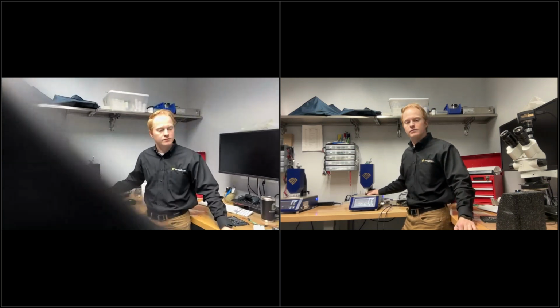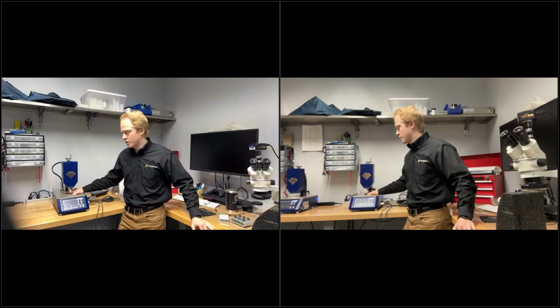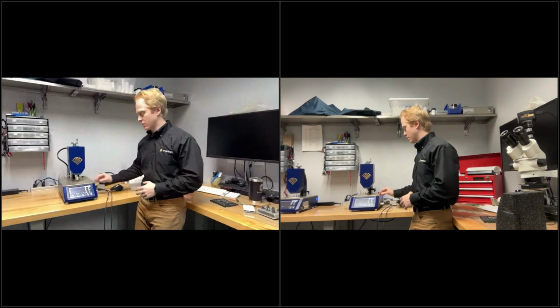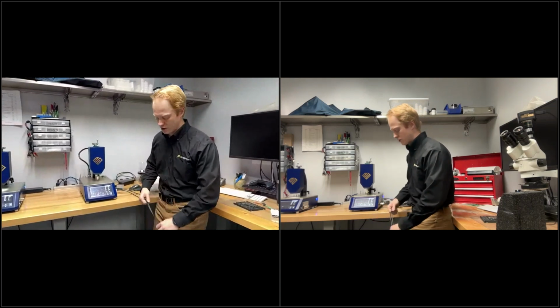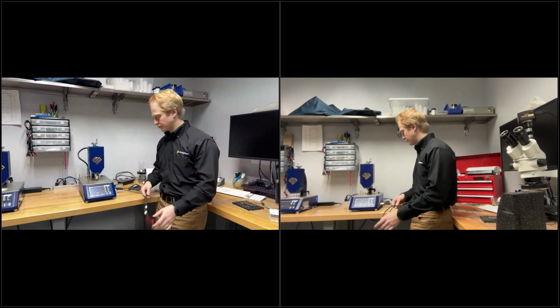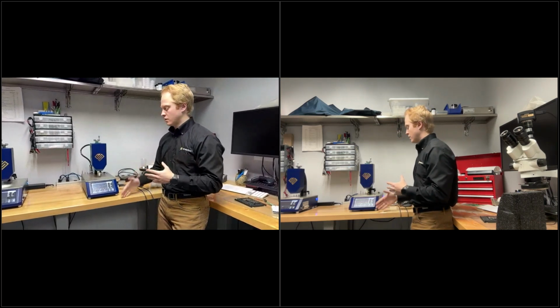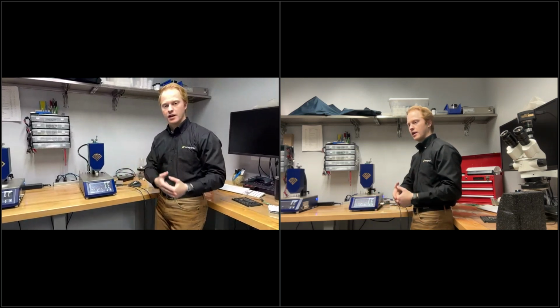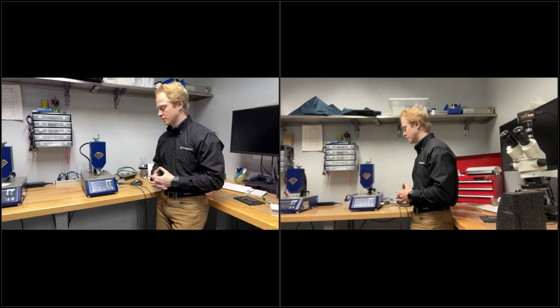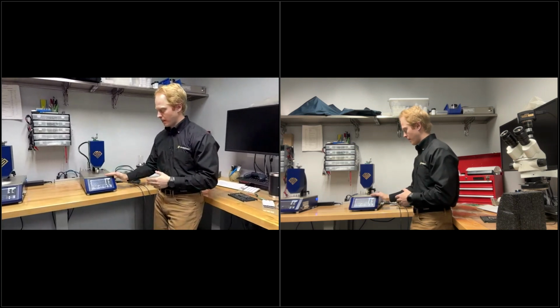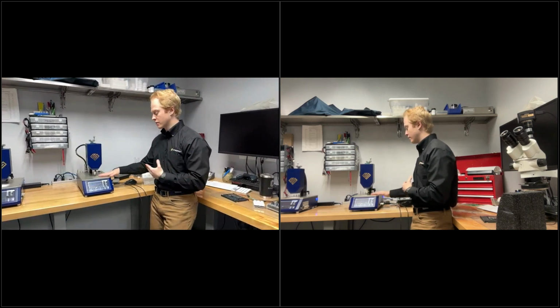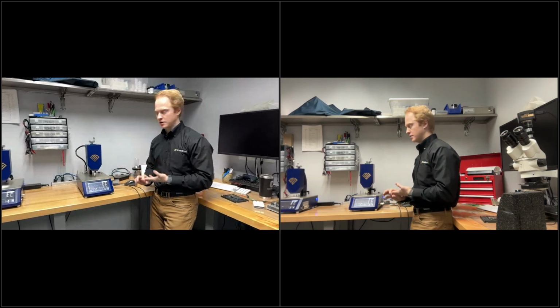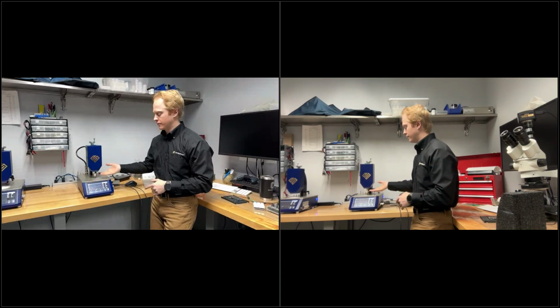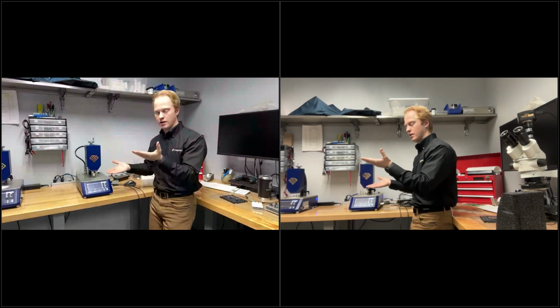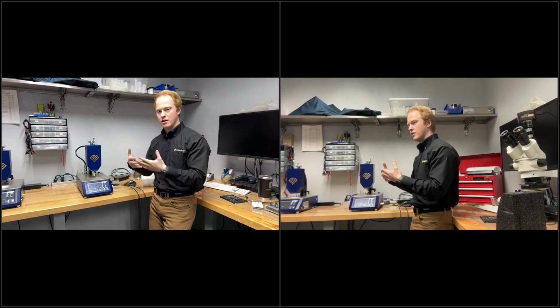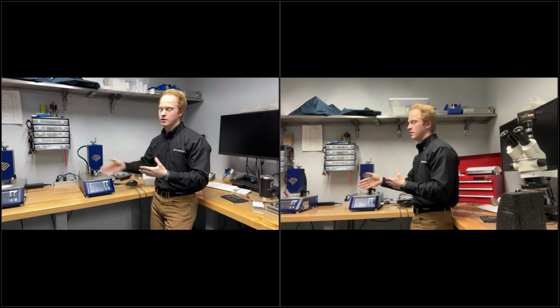Henry is asking, how easy is it to do the calibration? Well, that'll depend on which part of the calibration you're going through. There's two steps to it. Either you have the resistance calibration, in which case we ship the machine with a resistance decade box, if that's the additional accessory that you go with, and then you will calibrate in the machine the resistance level of the decade box to the read resistance through the resistance loop here. And that's how you do the resistance loop. For the force calibration, the additional calibration package that we have offers 3 NIST certified weights that you will hang off of the included teeter-totter force displacement calibration tool, and that will put a calibrated amount of force on the load cell, and then you will tare the load cell to the NIST certified weight that's on the end of the teeter-totter.